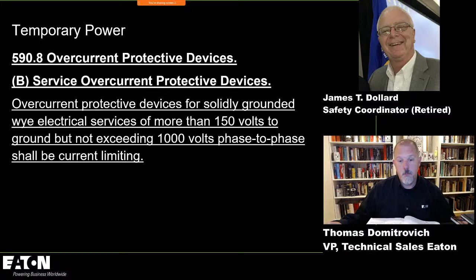I can tell you that as safety coordinator from 2001 to 2018, I saw multiple arc flash incidents. I can tell you that I didn't see any at 208. Can you get 208 to sustain an arc? The answer is yes. You need a significant amount of available fault current. You need a tighter arc gap and a smaller enclosure. But I can tell you at 480, 277, you will get arc duration on service equipment. I saw arc flash incidents on the load side of molded case circuit breakers, because that's what we're working with 98, 99% of the time, and the device would open. But when you get on the line side, it's not going to open.